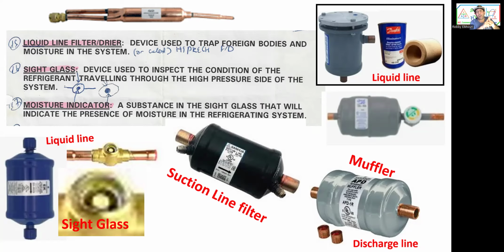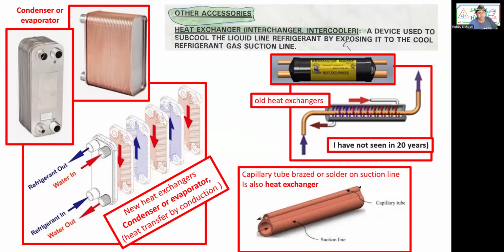Some only have one. You don't need two. You only need one because the other one you can get at the pressure of the compressor. Right? So that's how we know if the suction line filter is clogged. The liquid line filter, we know it's clogged by temperature, which is also rare, but it happened to me a couple of times. I've been doing this so long. I'll cover filter dryers again in detail in another class.